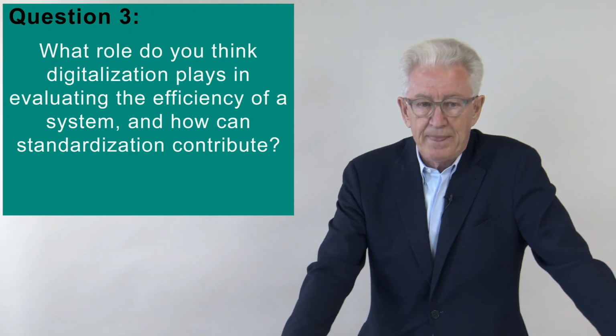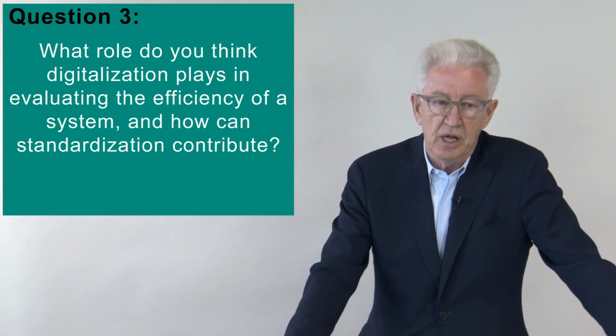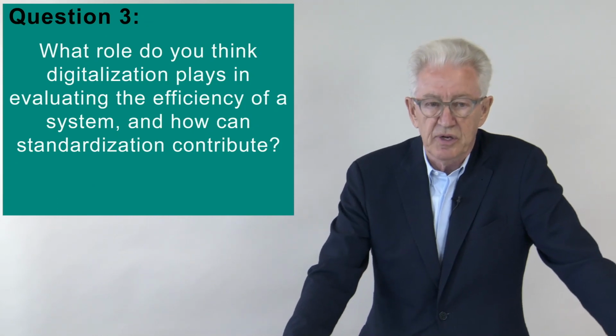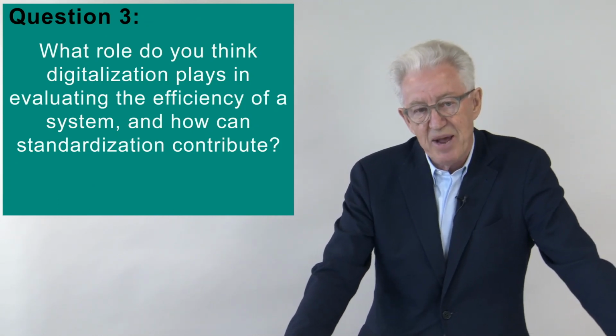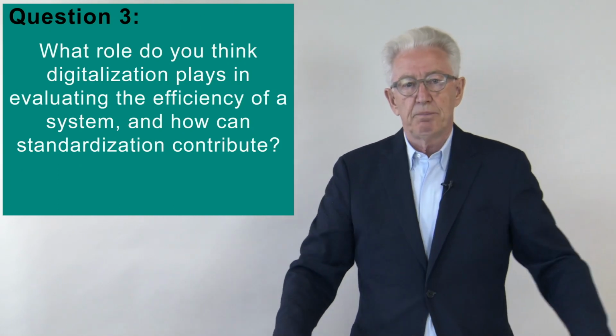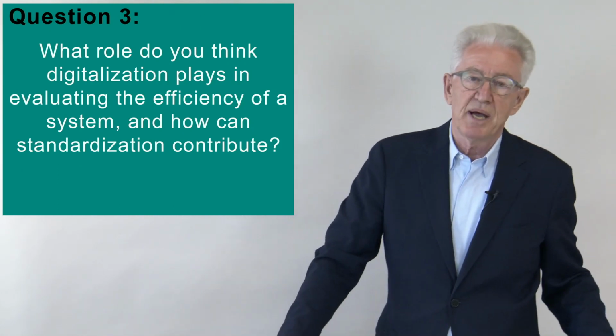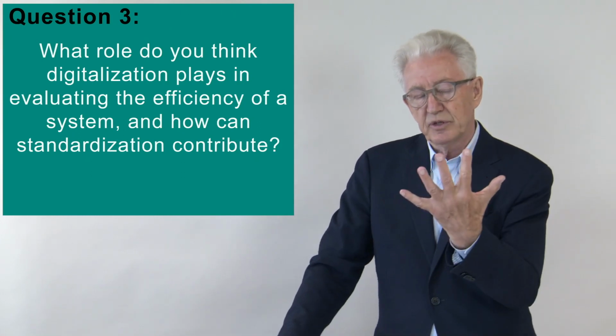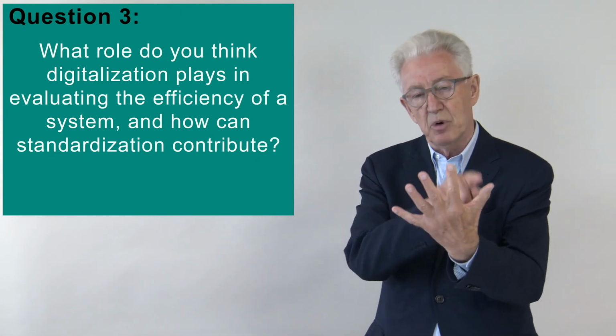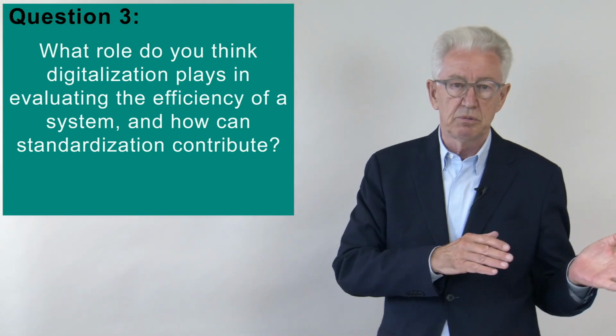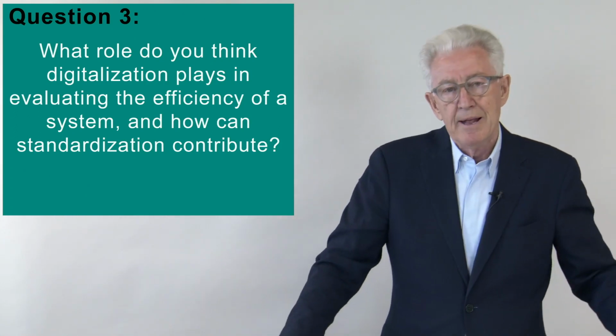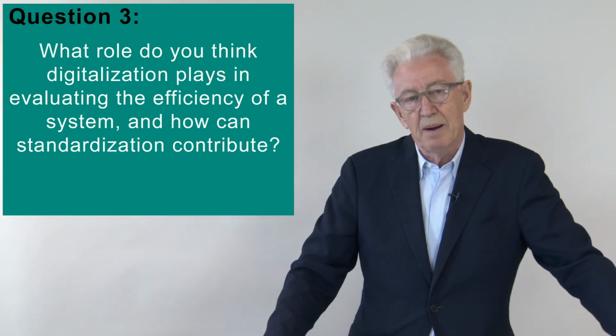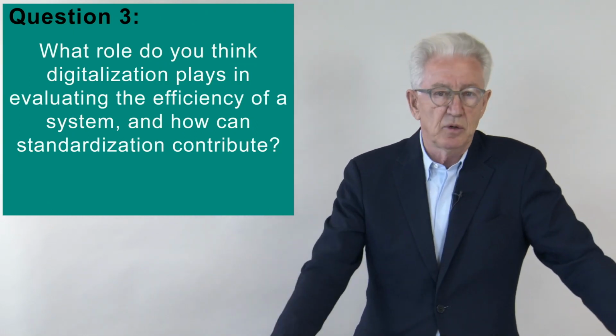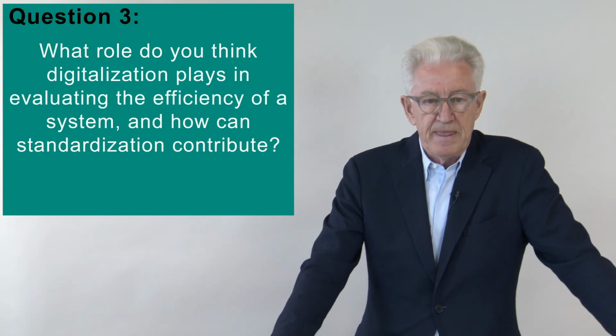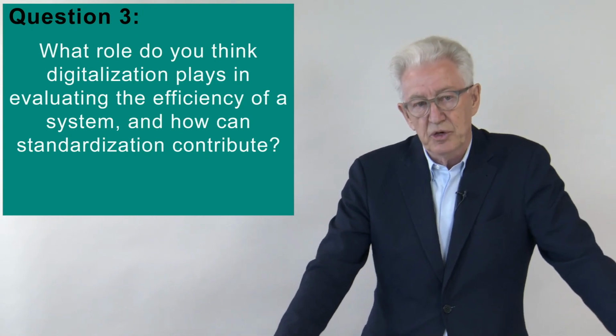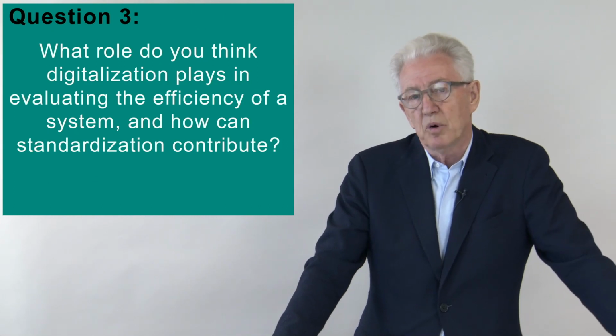When you have a new model, there is what is called an alternative determination of losses. It's used in the USA, the AEDM system. You can relieve part of the burden of the testing by requiring that, for instance for the motor over the whole range, you only test 5 motors at 5 given points between 0.1 kilowatt and 1,000 kilowatt. And then you have a simulation program that determines or interpolates all the points in between. Therefore, standardization can contribute, and digitalization is certainly a very important point.